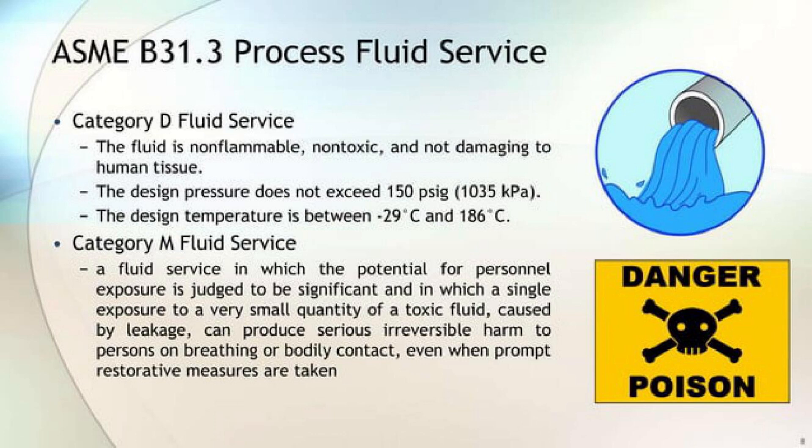What is ASME B31.3 Process Fluid Service? Here are some categories. Category D Fluid Service: the fluid is non-flammable, non-toxic, and not damaging to human tissue. The design pressure does not exceed 150 PSIG (1035 kilopascals). The design temperature is between minus 29 degrees and 186 degrees.